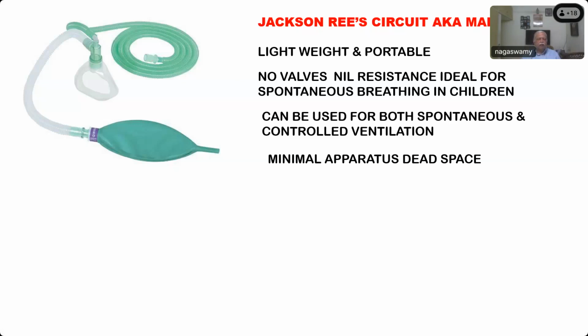of the expiratory valve. So here, if you see, this is the adapter for the mask or the endotracheal tube. Okay, and the fresh gas flow is coming almost into the mask or into the endotracheal tube. So only this portion, if you use a mask, this mask is going to be the apparatus dead space. Or if you use an endotracheal tube attached to that, only the volume of the endotracheal tube is the apparatus dead space, because the fresh gas flow is almost entering here. And imagine a Magill circuit, where the expiratory valve is also very close to the mask or the endotracheal tube. So distal to the expiratory valve, up to the mask or the endotracheal tube, is the dead space. Okay, so the point of entry of fresh gas flow or the location of the expiratory valve is where the apparatus dead space will end.